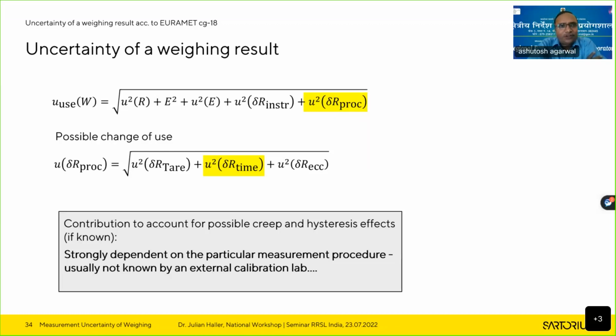Another question is, can we calibrate heavy capacity weighing balances by using M1 class weights? I think it is not possible, because, for example, if we are calibrating a weighing machine of, let's say, 1 ton with 10 gram resolution, it requires at least F1 class weights to calibrate. What is your suggestion, sir?